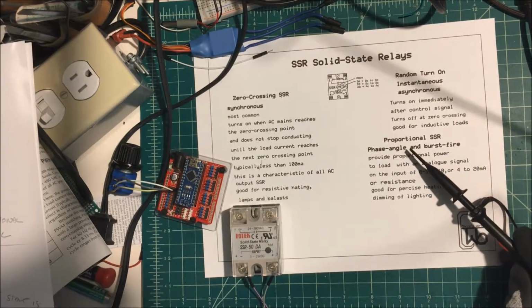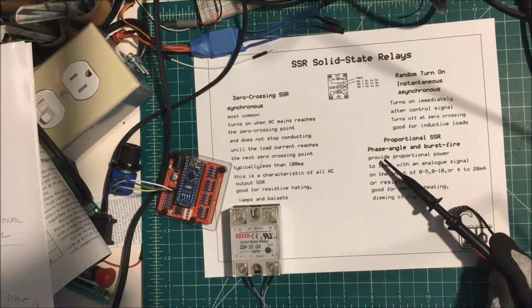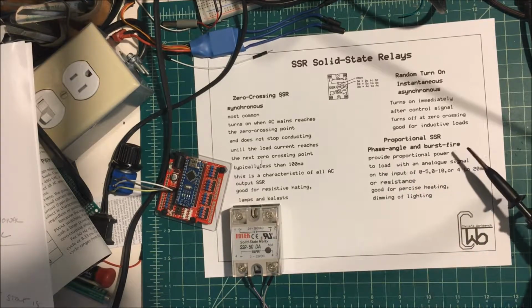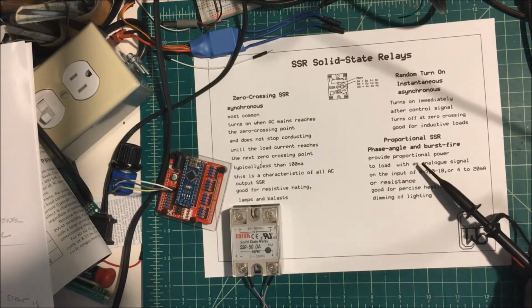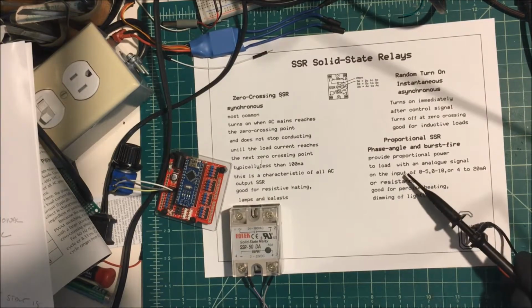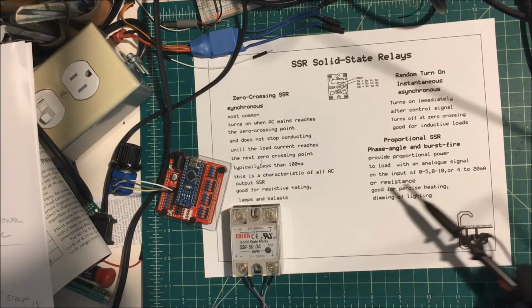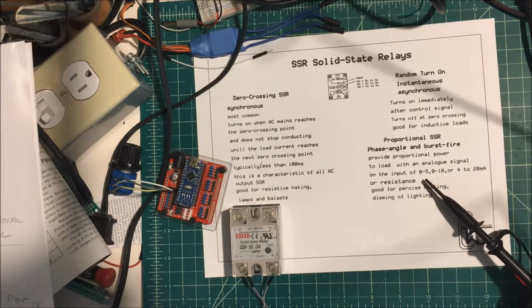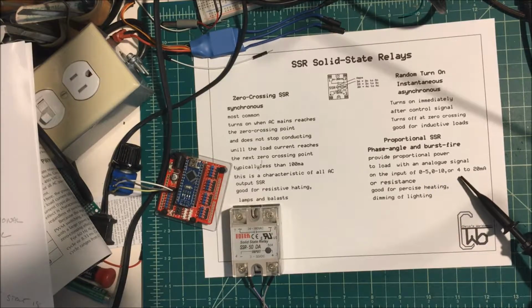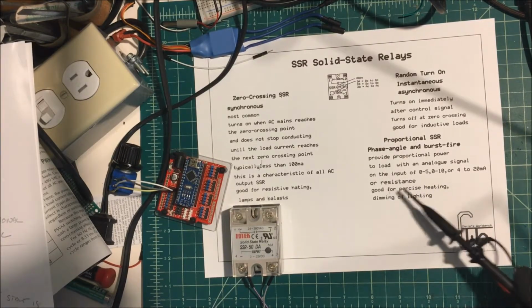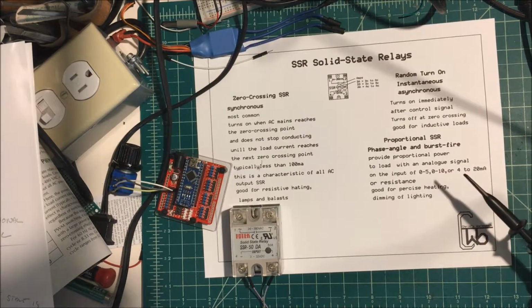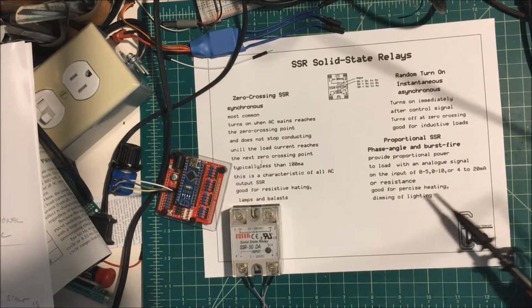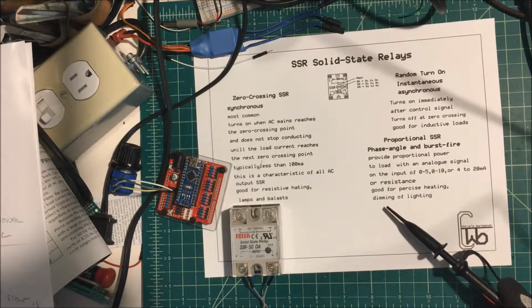Then we have the proportional SSRs, and they come in a phase angle or burst fire, and they provide proportional power to the load with an analog signal input. So it could be 0 to 5 volts, 0 to 10 volts, 4 to 20 milliamps, or just a resistance under a pot. These are good for precise heating and dimming of lighting.